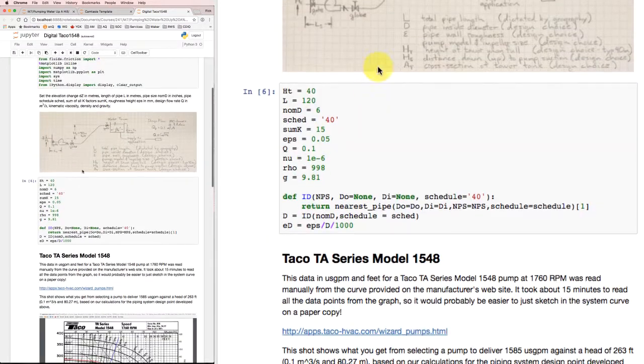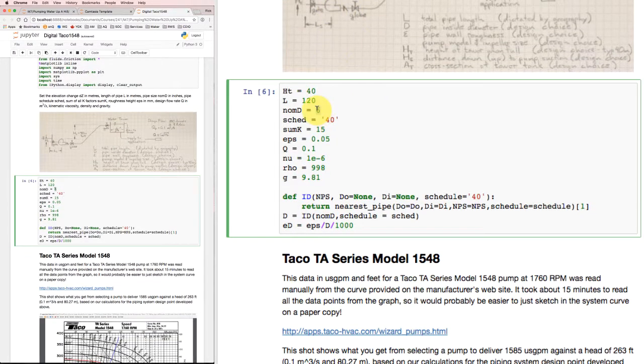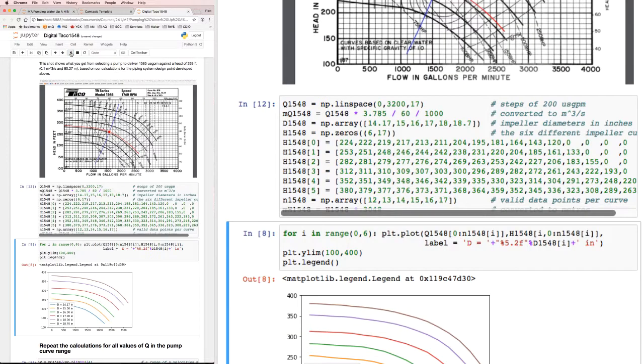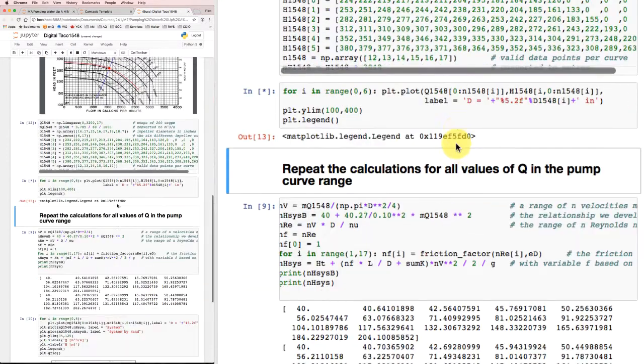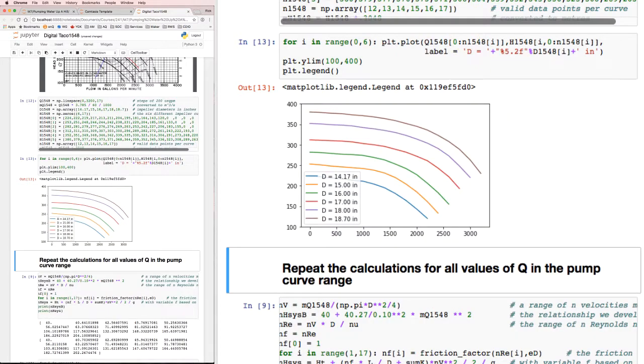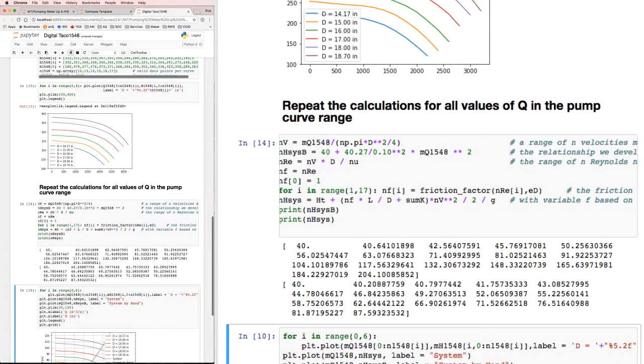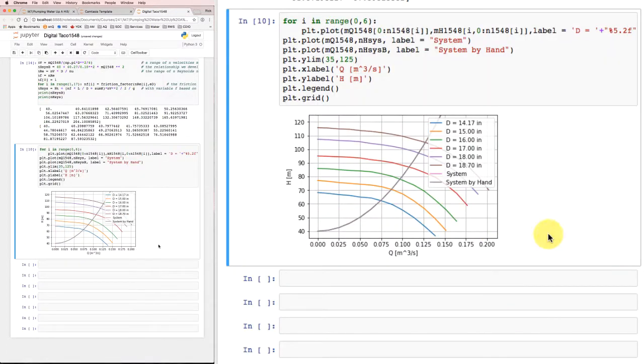So I could go up here to the top and where I had a 6-inch pipe here before, I could make this an 8-inch nominal diameter pipe. I'll repeat the calculation, fill that in, get the right diameters now. I've got my pump curves and they should be all still the same. I can repeat the calculations over a range of values and now I should see some changes in what I get out of my plot.